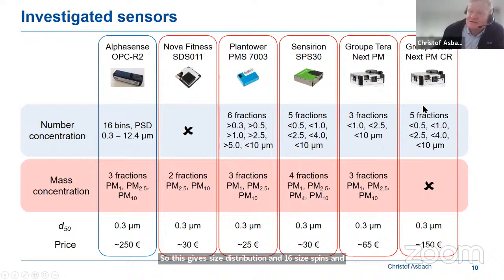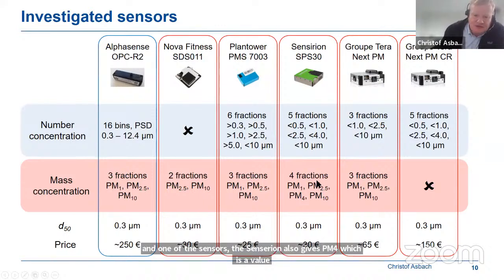All the other sensors that we tested are advanced photometers, and we see that all but one deliver number concentrations in different fractions, from 3 fractions up to 6 different size fractions. And all but one other sensor deliver mass concentrations in between 2 and 4 fractions. So every one of the sensors delivers PM2.5 and PM10. Some also deliver PM1. And one of the sensors, this is Sensirion, also gives PM4, which is a value that's typically used in occupational exposure studies.